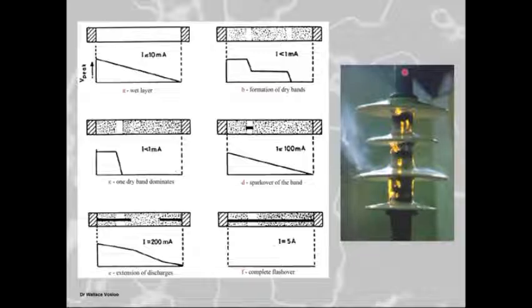Okay. So let us see. Here is a little insulator. You can see here is the dead end side, here is the live side. And this insulator tells quite a bit of a story. Normally, with an insulator in clean conditions, you find there's very good insulation in between, normally in the hundreds of megohm resistance from this side to that side, and it's got excellent insulating properties.